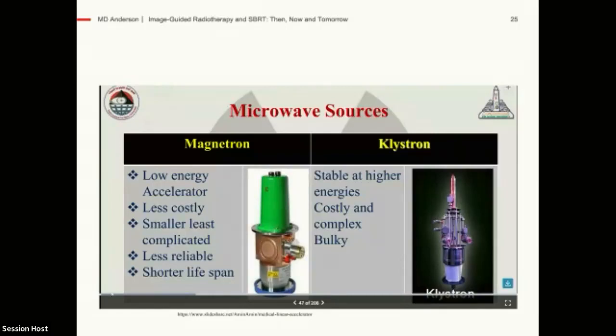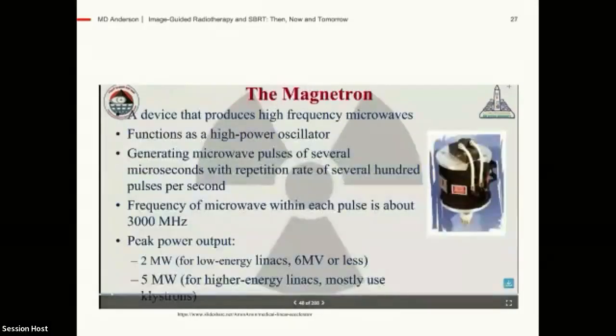This is what the microwave sources look like, and there are different characteristics about them. If it utilizes a magnetron for the microwave source, that's for low energy accelerators. They're less costly, smaller, and usually meant for older type systems. Nowadays most modern systems use the klystron, which gives you stable, higher energies. The magnetron produces high frequency microwaves and functions as a high power oscillator.